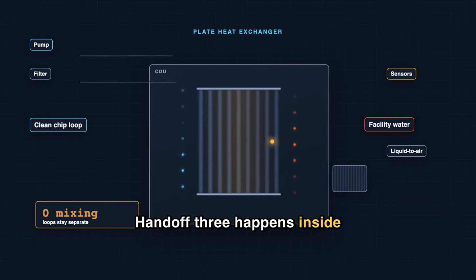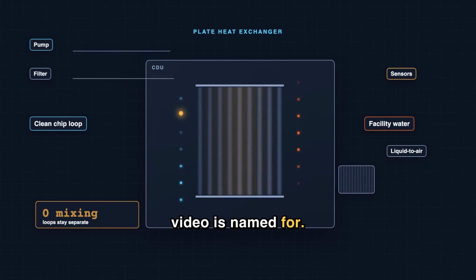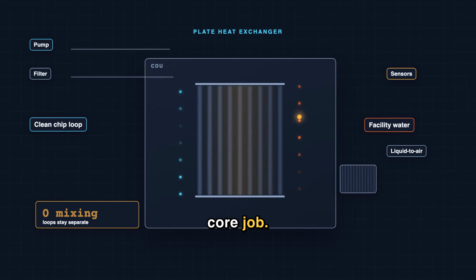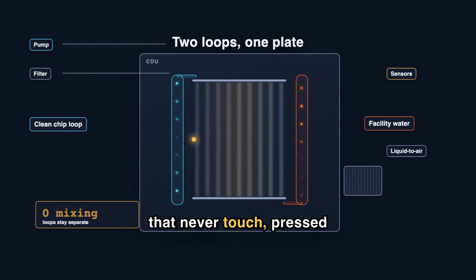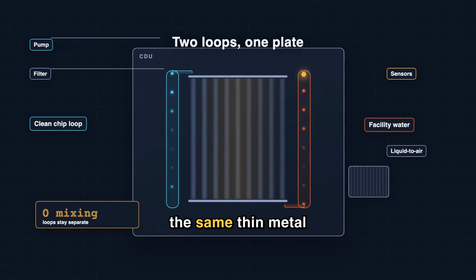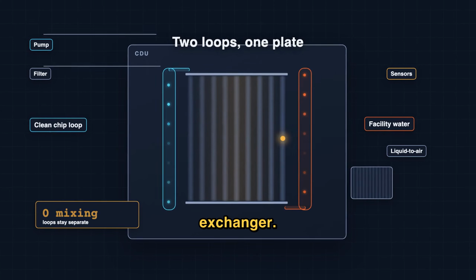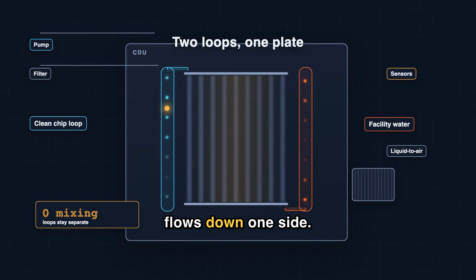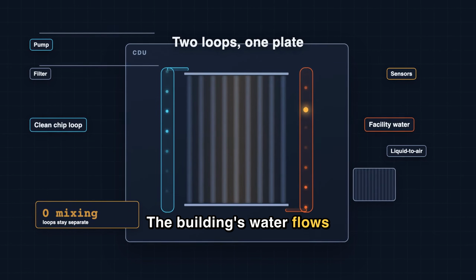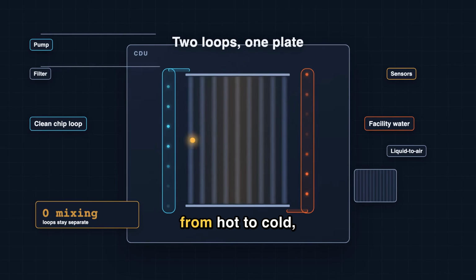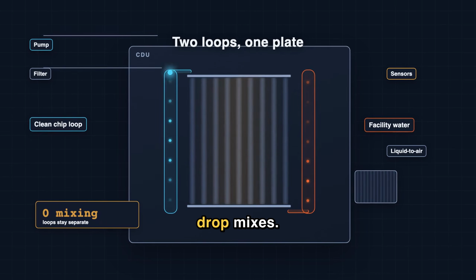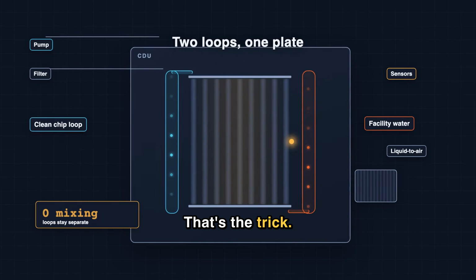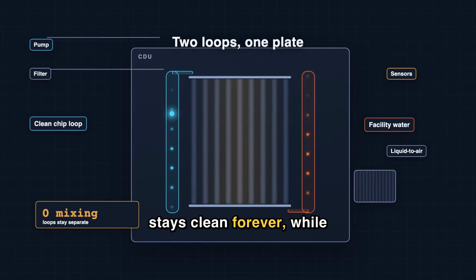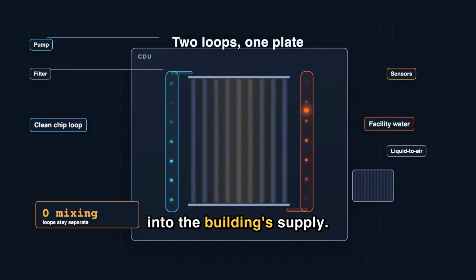Handoff 3 happens inside the box the whole video is named for. This is the CDU's core job. Picture 2 separate loops that never touch, pressed against opposite sides of the same thin metal plates. A plate heat exchanger. The clean chip loop flows down one side. The building's water flows up the other. Heat crosses the metal from hot to cold, but not a single drop mixes. That's the trick. The chip's private loop stays clean forever, while still dumping its heat into the building's supply.